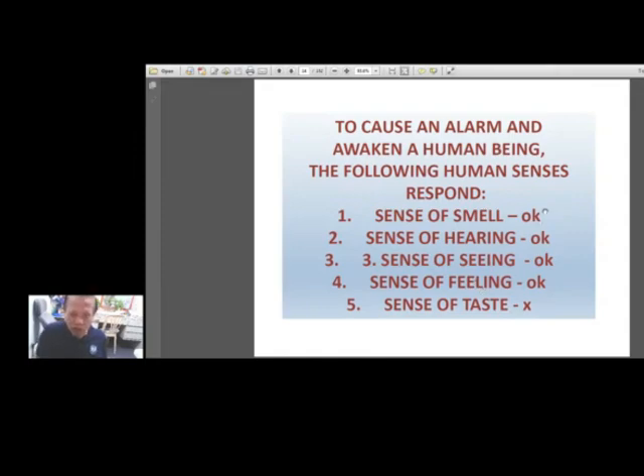So as of today, inside the burning room, you have the sense of smell, then the sense of hearing is part of the FDAS today, and the sense of seeing is also part of the FDAS because of the alarm light, the rotating beacon, and the LED lamp. And the sense of feeling can already be included, but only in the addressable type. In the conventional, it is not yet possible unless they can modify it so that when a conventional fire alarm control panel is actuated, it can also send a signal to a SIM card. It is possible, but as of today, it is a little harder to realize.